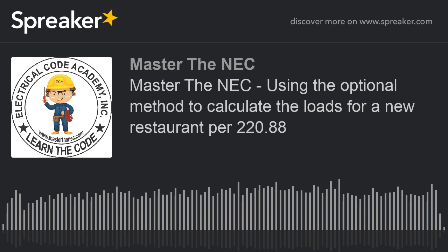All right? But you have to meet the caveats, and there are 3 caveats there that you need to be aware of. We're not going to go into those, but just a reminder that you can only protect service conductors for overload protection. Okay? All right. And of course, we talked about the feeders not required to be a greater ampacity than the service conductors. Again, that does not apply in our scenario where we didn't have a main power feeder, whereas we had a remote distribution panel that ultimately downstream had multiple feeders coming out of that.